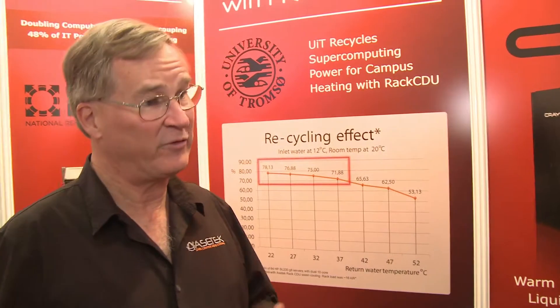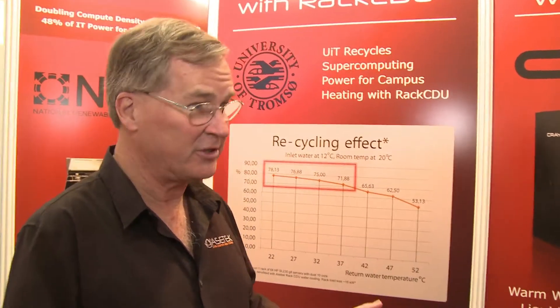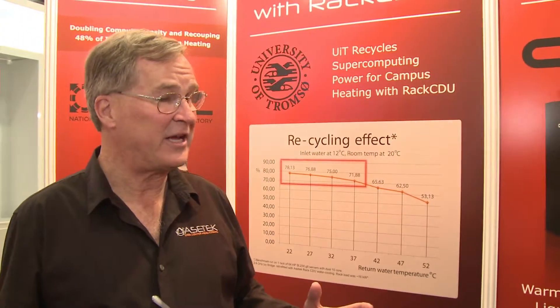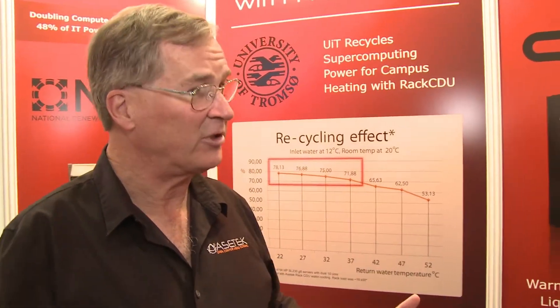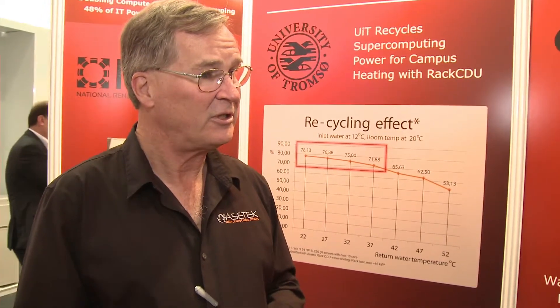That's really the exciting thing for us here at the show. We've talked before about the technology, but what we're really talking about here this time is deployments, and we've gotten a number of them. We started with a deployment at Lawrence Berkeley National Labs last year, where we deployed 38 Cisco units with Intel processors and did a variety of tests. Those have been put into a white paper now available on the Berkeley website, describing how this type of hybrid liquid cooling performs — cooling the CPUs and memory, with air cooling taking the remaining heat out of the building. That makes a very cost-effective implementation.